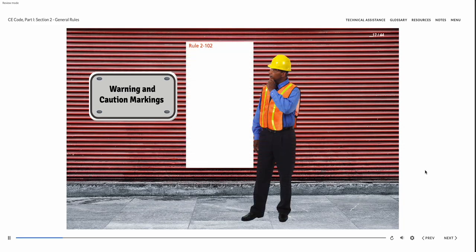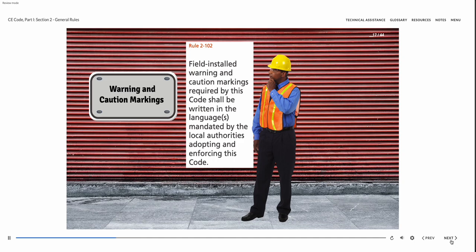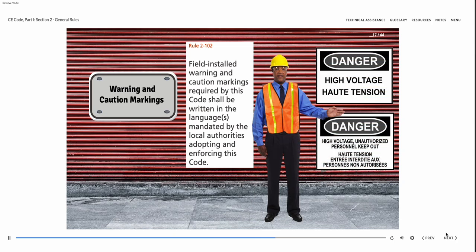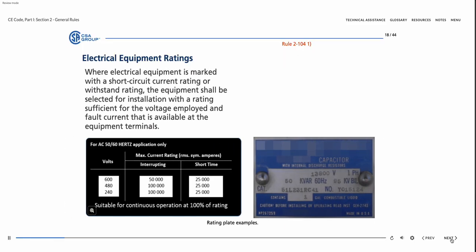To avoid safety hazards for individuals working on electrical equipment, Rule 2-102 requires that any field markings required by the code should be done in both official languages in Canada, where it is required and enforced by the local authority having jurisdiction. When electrical equipment is marked with a short-circuit current rating or withstand rating, the equipment shall be selected for installation with a rating sufficient for the voltage employed and fault current that is available at the equipment terminals.